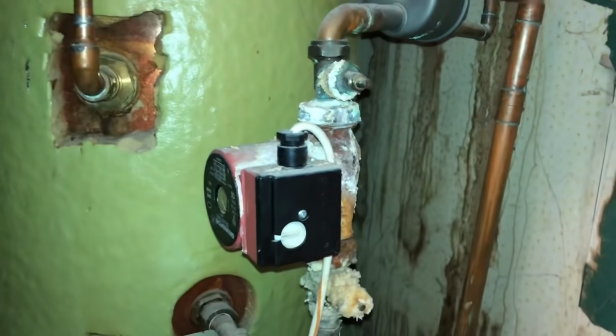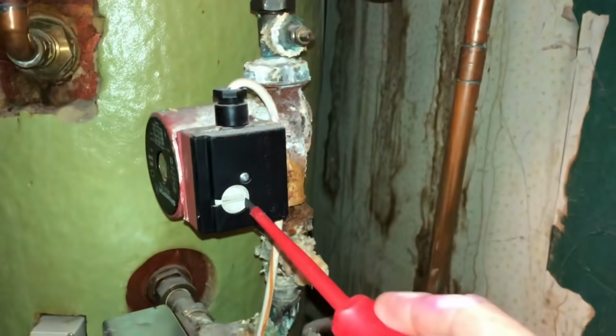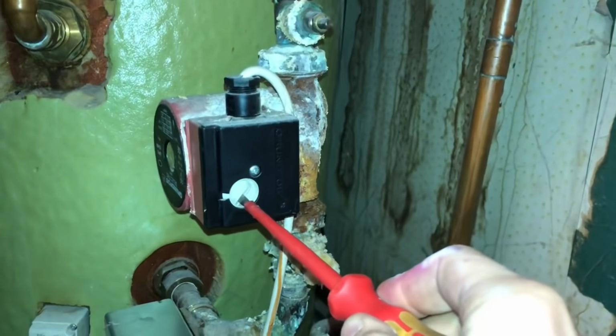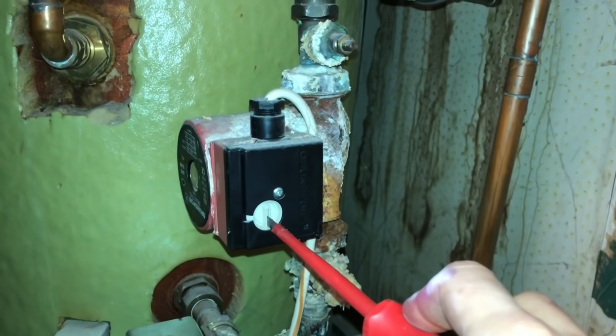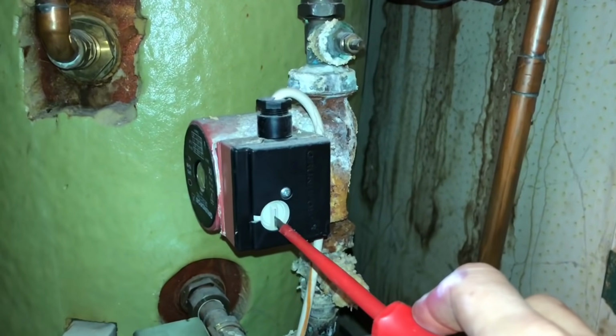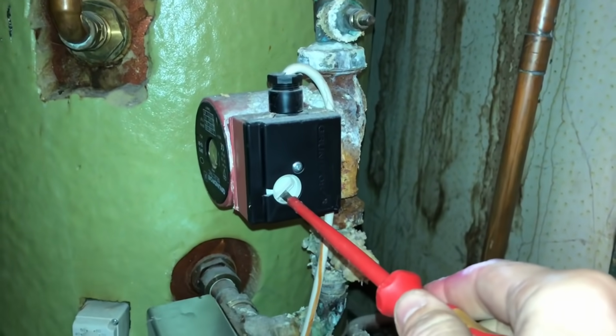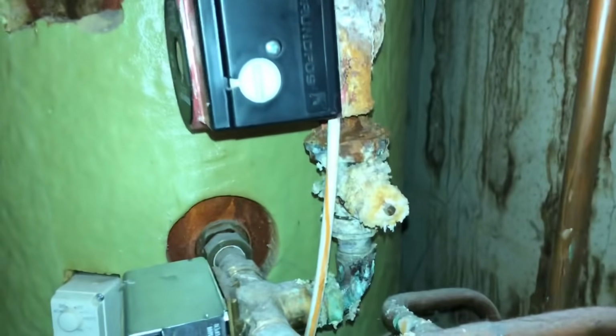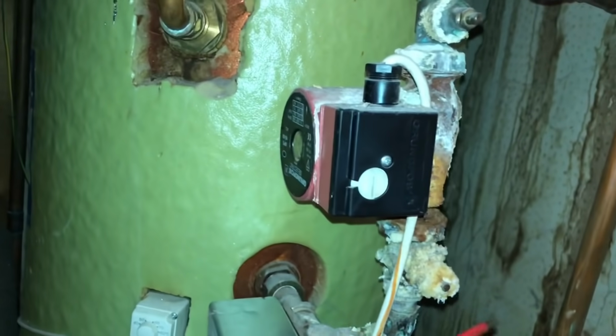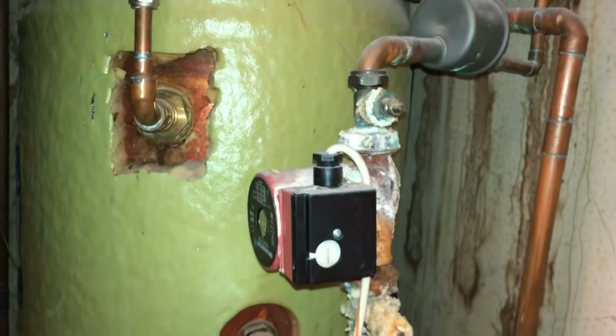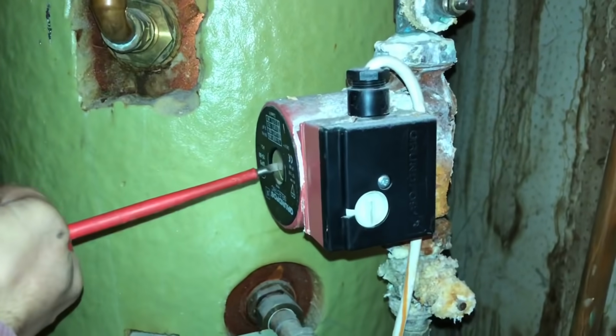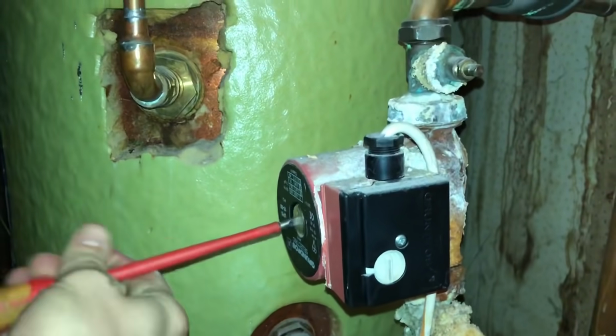So obviously looking at this pump, you can tell that it's knackered, it's been leaking, it looks old. It's not red hot. One of the telltale signs of a pump not working properly is it will be absolutely scalding hot, because the motor is working too hard. On this one it is actually spinning. It sounds like it's spinning on all 3 settings. So a great way to confirm that a pump isn't performing as it should is to take the spindle out of the middle.